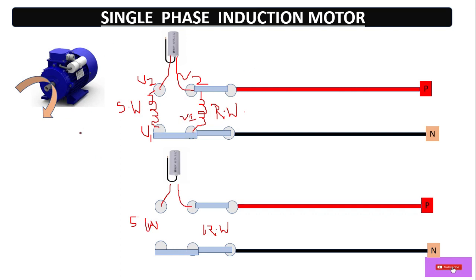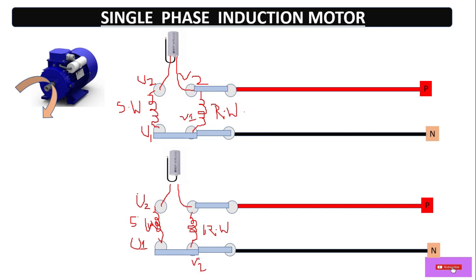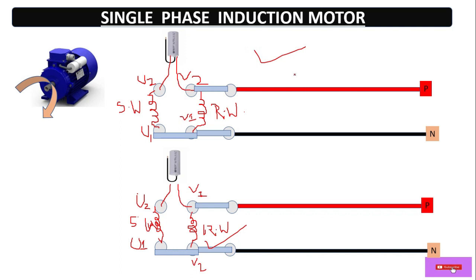Now let's change the direction of this single-phase induction motor. The starting winding terminals U1 and U2 are left as they are. The neutral and strip connection remain the same. Simply interchange only the running winding terminals: V2 goes to this terminal and V1 goes to this terminal. Exchange the running winding terminals — V2 connects over here and V1 connects over here. In simple terms, just exchange the running winding terminals to change the direction.